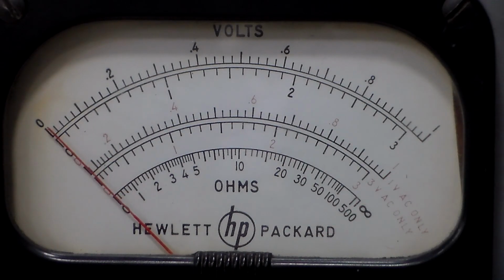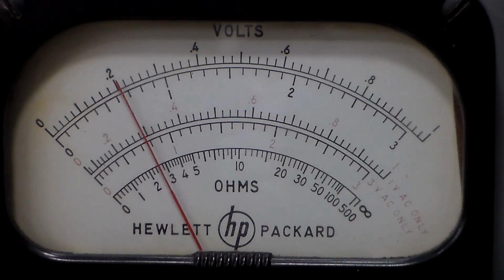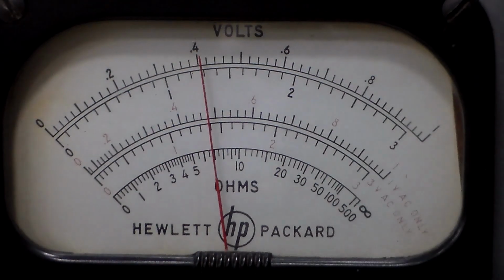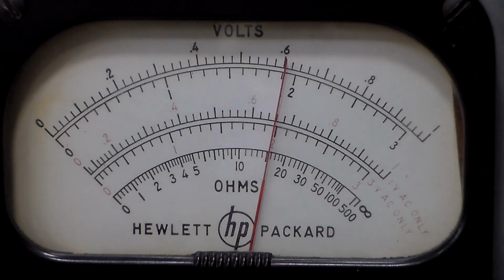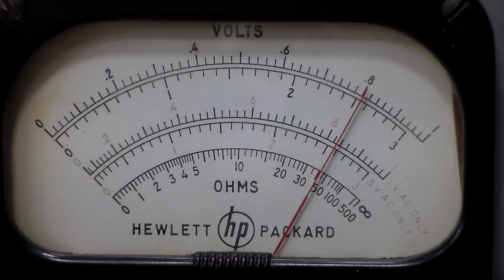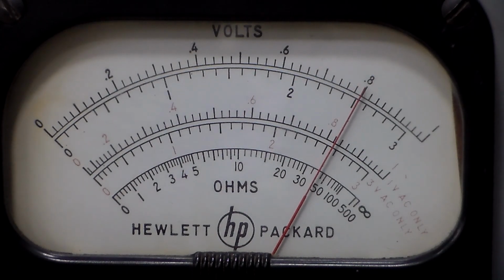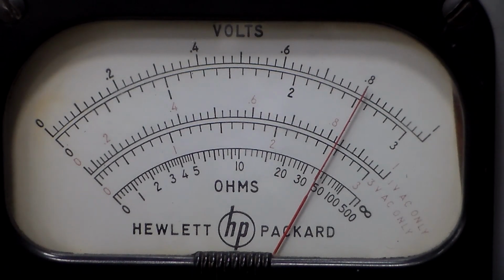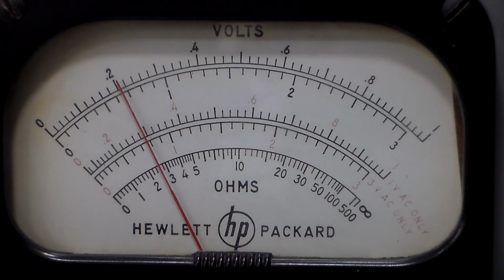Now if I go to 0 again, we've got 0 showing. Okay, now what we'll do is try some part of the way up the range. So let's go for 200 millivolts, and it's just a hair over. 400 millivolts. It's just slightly high again. 600 millivolts. Again slightly high. 800 millivolts. So we could actually slightly reduce our gain to try and improve over the whole range. So now if I go back to 200, it's still a fraction higher there.